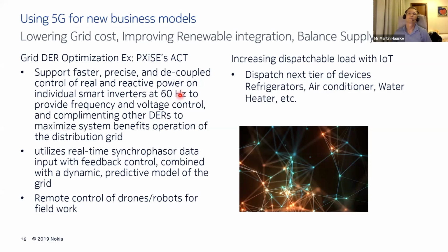A micro PMU that enables inverter control. As I mentioned earlier, how can inverter control enhance better integration of DERs? In Germany, we are actually wasting 9% of DER output currently because the grid cannot take it. The curtailment is quite severe, which is a waste of customers' investment, but also a lost opportunity for cleaning up the grid. So we use synchrophasor data for feedback control.